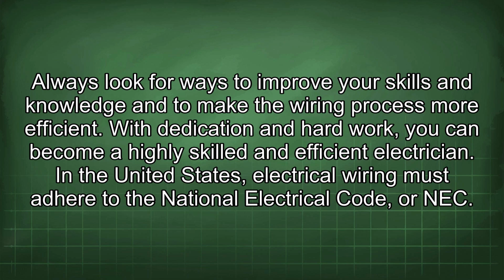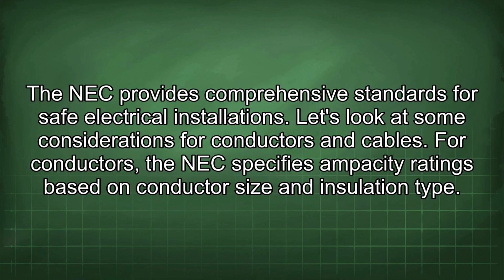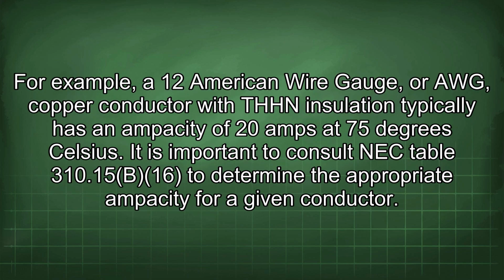In the United States, electrical wiring must adhere to the National Electrical Code, or NEC. The NEC provides comprehensive standards for safe electrical installations. Let's look at some considerations for conductors and cables. For conductors, the NEC specifies ampacity ratings based on conductor size and insulation type. For example, a 12 American wire gauge, or AWG, copper conductor with THHN insulation typically has an ampacity of 20 amps at 75 degrees Celsius.